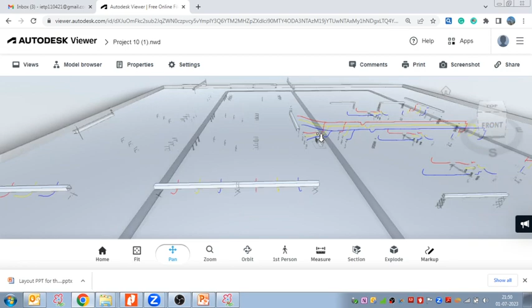So coming back to this view, here we have the transformer. For the transformer replacement, we need to plan the road near to the transformer, and here we make the rail-cum-road, which generally we take as 5.5 meter. That we have to check against the size of the transformer, but usually we take 5.5 meter road. This road is required near the transformer or near the reactor.